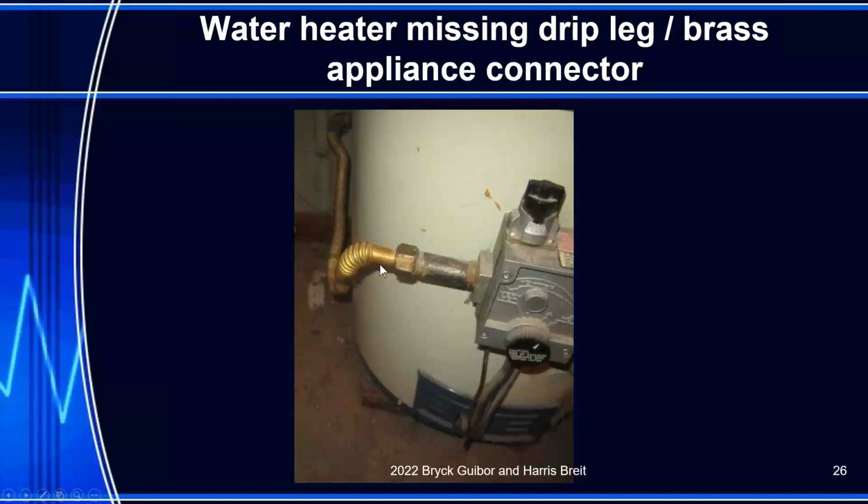Okay, here we go. This has old yellow brass. There's been a recall on old yellow brass for about 15 or 20 years. All of it comes now epoxy covered or stainless steel. So we write these up all day long.